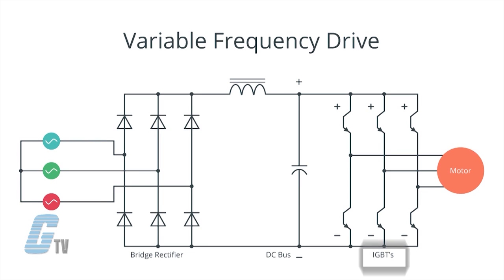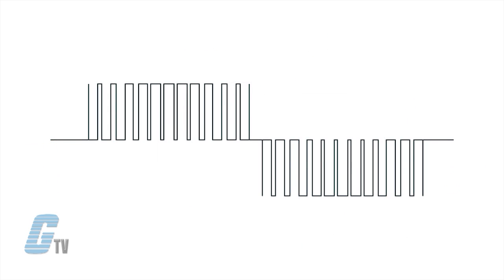The DC current follows along to a group of switches or transistors that open and close to allow for positive or negative voltage output. This presents a PWM voltage pulse in a square shape, and since it is done multiple times with varying degree, the square shape pulse will increase and decrease in width.